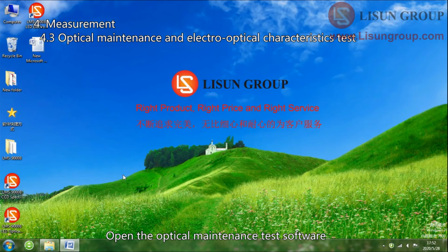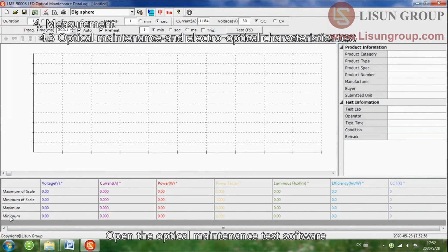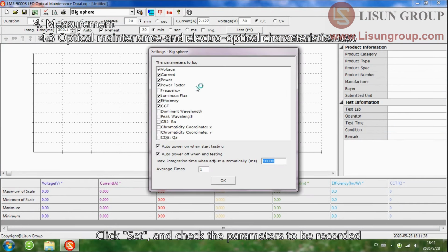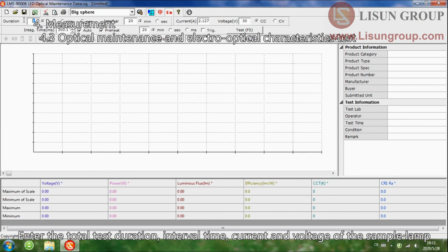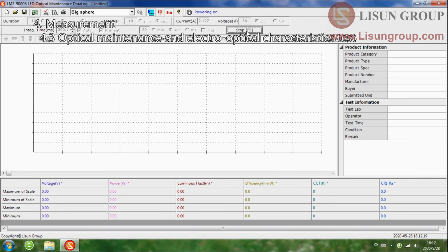Open the optical maintenance test software. Select the corresponding integrating sphere, click Set, and check the parameters to be recorded. Enter the total test duration, interval time, current, and voltage of the sample lamp. Choose CC constant current or CV constant voltage mode. Enter the preheat time, and click to start the test.